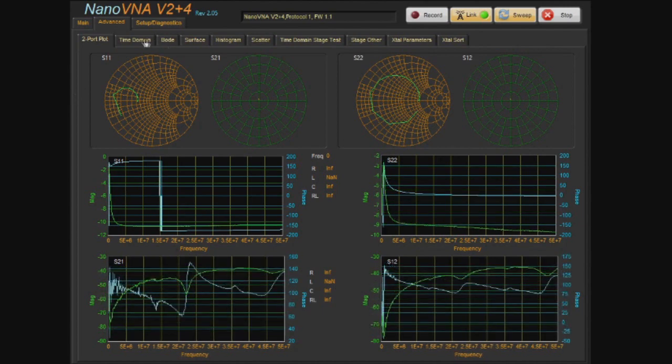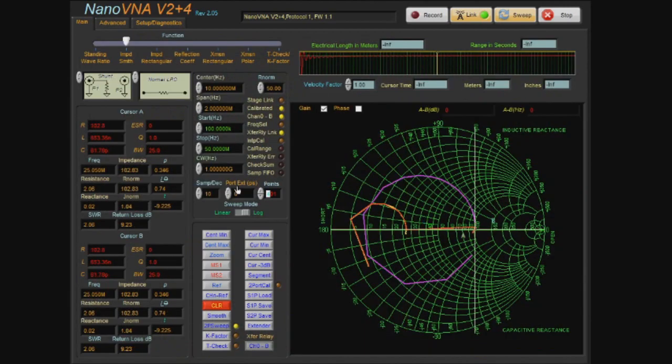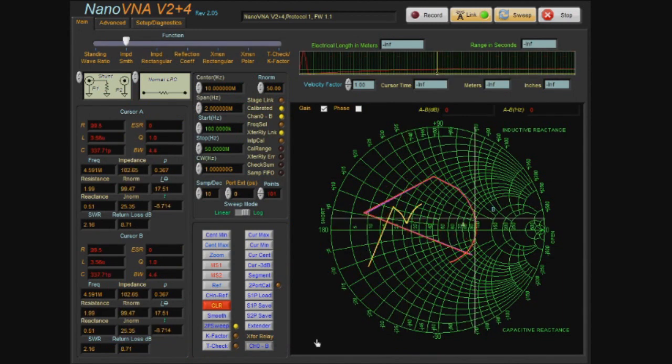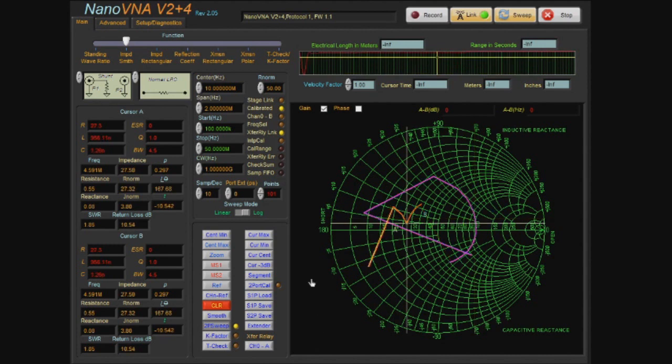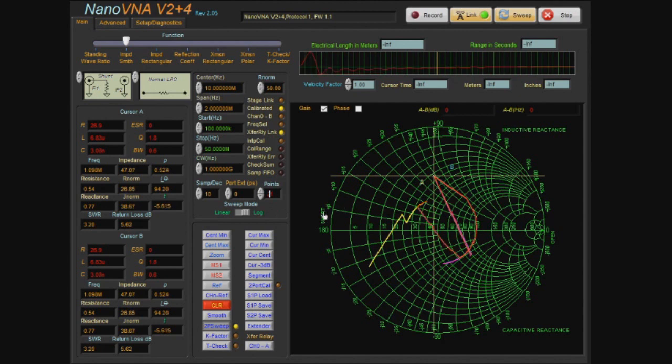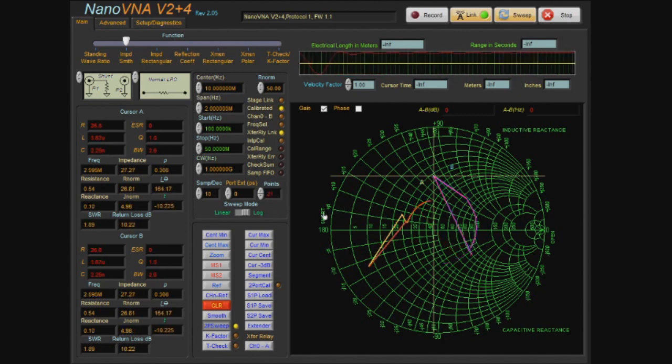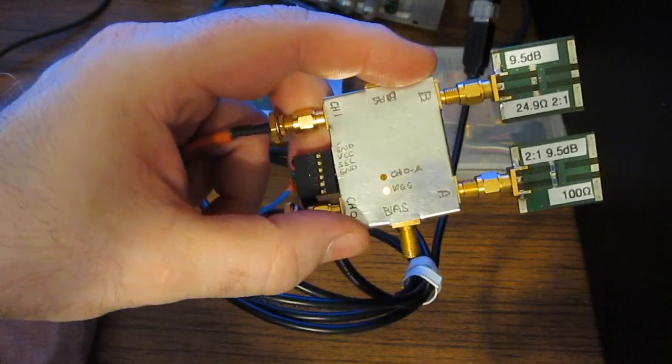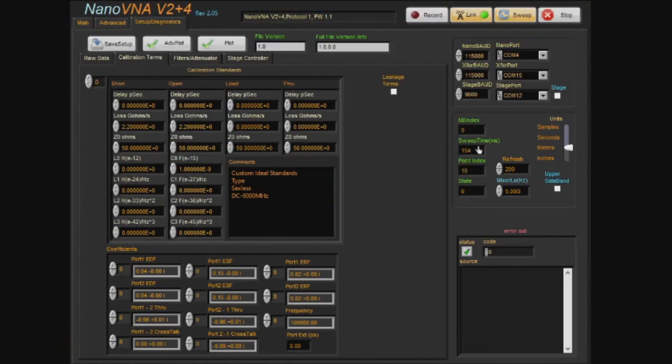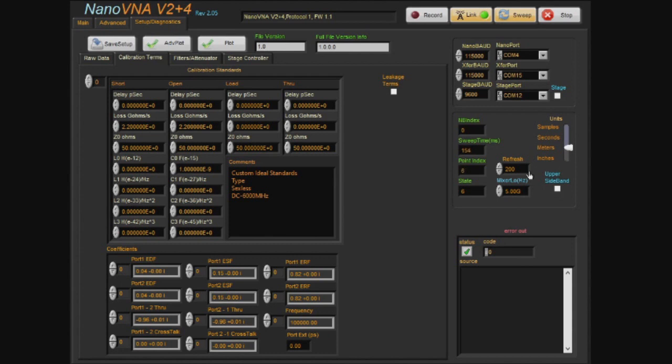Let's go to advanced and now we can see all four s-parameters being shown. Let's change the number of data points to 100. You can see it's switching between the two states four times faster as we would expect. Let's take this down to 21 data points, and you can see now it's basically not changing states. There's another setting preventing this from running faster. If we go to setup diagnostics, you can see this refresh is set for 200 milliseconds. That's how often the software services the foreground task. The sweep time right now is 152 milliseconds, so the sweep time is faster than what we're updating the foreground task.